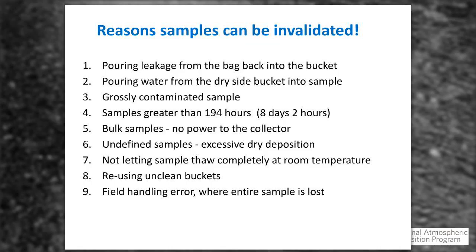As Chris said, during the holiday season, samples greater than 194 hours. If you know you're going to be away, and your backup operator will not do it, we try to get back on the 7-day schedule. If you've got to go Wednesday to Wednesday, Monday to Monday, however you've got to do it to stay within the 194-hour spectrum, go ahead and make a note. Call us, let us know that's what you're up to, or email us as well.